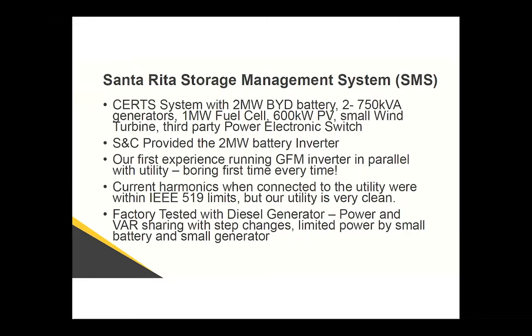So in addition to running just sort of with utility, we wanted to see how we shared with a diesel generator. So in our shop, we did some testing with a diesel generator. The top curve is our A-phase voltage. This is a 3-phase system. We have all 3 voltages, but they all look the same, so I just have the A-phase. Down below, we have the current out of the inverter, and that's in red. In pink, there's the power coming out of the inverter, and that's been offset so that you can see it. And then down in black at the bottom is the frequency of the inverter, and that's also been offset.